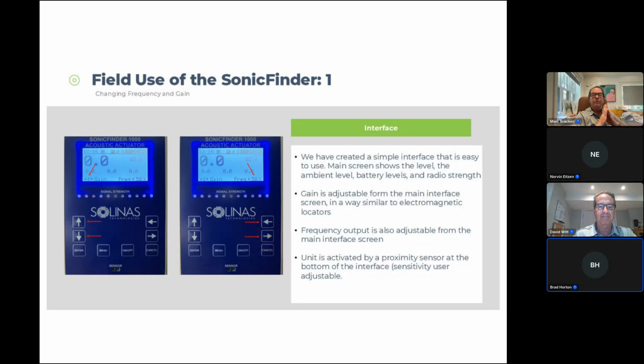All right. Now, the user interface of this is really simple. Looking at the screen, you see the large numbers there in the middle. That is your signal strength, or actually your amplitude of sound in our case. There are some other icons on there. It gives you a real-time sound reading, so you know what your floor noise level is. There's a histogram, which records the last 3 peaks or numbers that you got on the instrument, so you can track it well, and you don't have to keep the numbers in your head.